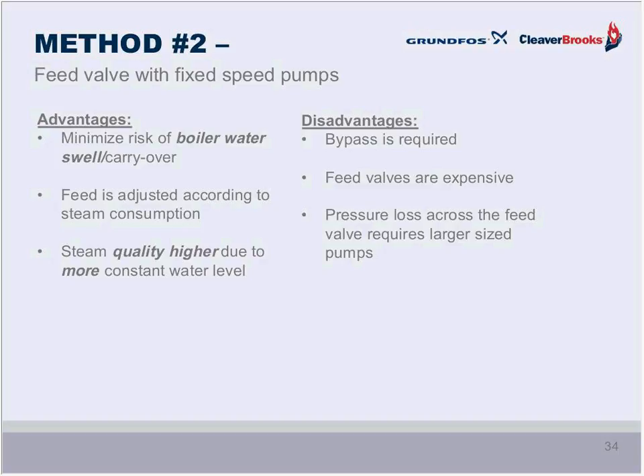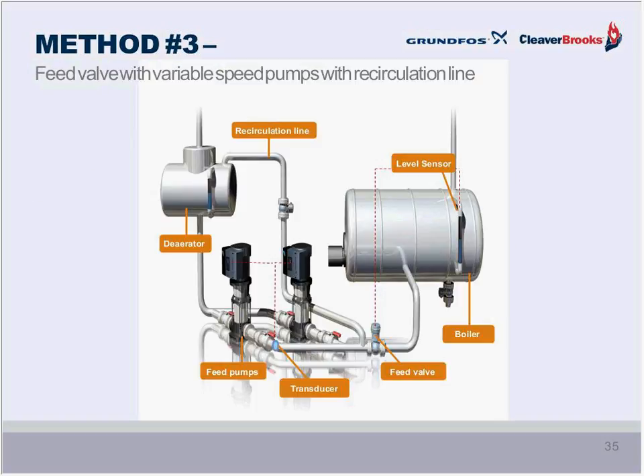Let's now take a look at the third method. Now, we've still got a feed valve, and we've still got a recirculation line, but these are variable speed pumps. We're still controlling the water level in the boiler with that feed valve, and its position is being controlled by a level sensor in the boiler. We're using a variable speed pump here, like I mentioned. This method also requires that the pump is set to continuous operation. So we, again, have that bypass line from the pump back to the deaerator tank or a vented tank for when the boiler's not calling for water, or when the water that's being called for is a low rate, because that puts the pump too close to the deadhead.